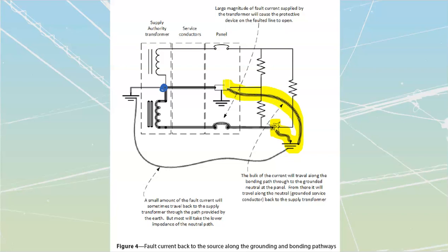That's going to be the bare copper conductor, the conduit sheaths and stuff like that. That all travels back to my neutral bus, which is tied to the panel, which then allows us to complete that circuit, to deliver it back to the transformer. That is ultimately the purpose of that bond strap and bond screw connection: to deliver fault current back to the neutral itself. So we see we've got a complete path.